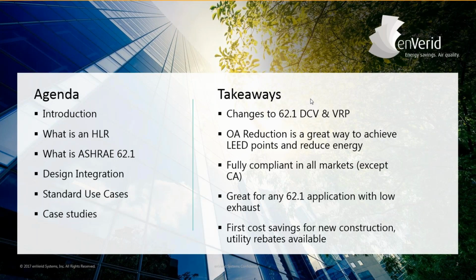Really what I'd like everybody to take away from today is how the indoor air quality procedure differs from demand controlled ventilation, where you're putting sensors in individual spaces, and ventilation rate procedure. We'll talk a little bit about the changes to 2019 ASHRAE 62.1 that are particularly relevant. We'll talk a little bit about applicable LEED points for deploying the indoor air quality procedure. Many folks on this phone call might be familiar with the fact that you can get 1 LEED point for increasing outside air versus baseline by 30%. Well, by actually reducing outside air by up to 60%, you're eligible for up to 12 LEED points on new construction and up to 17 LEED points on existing buildings. So it's a huge, huge LEED point generator here when you're looking at the indoor air quality procedure.